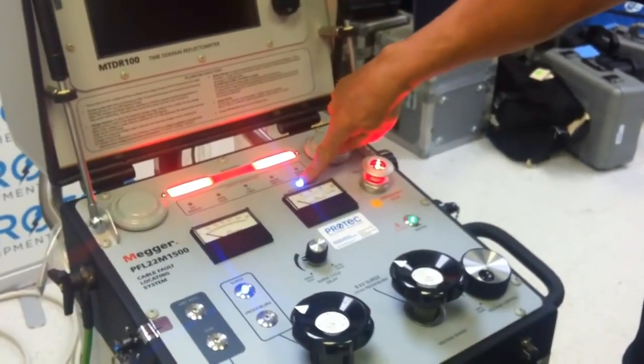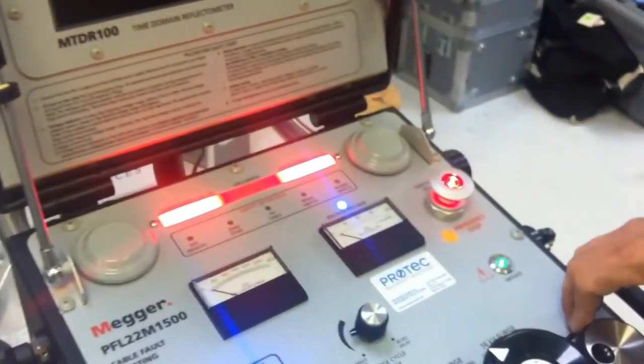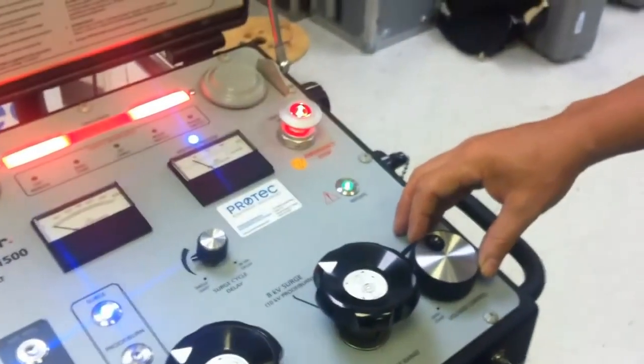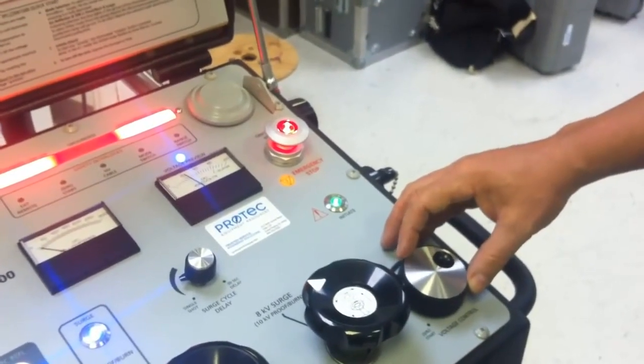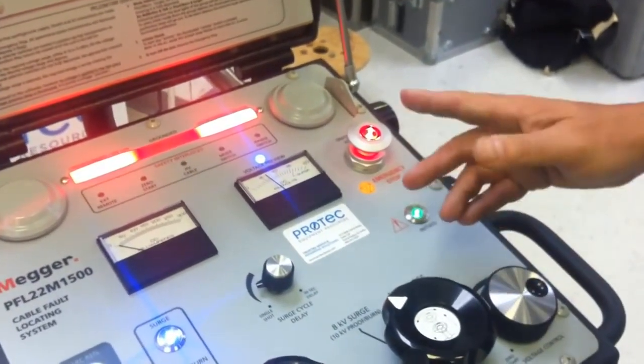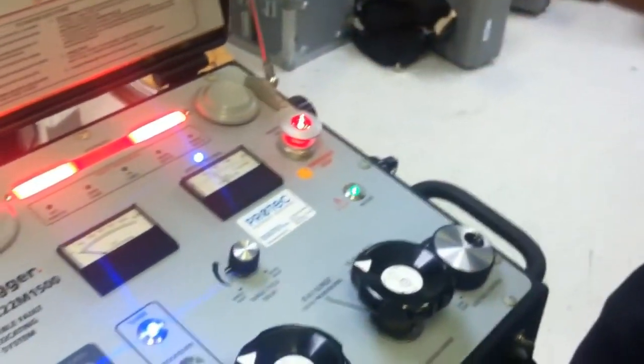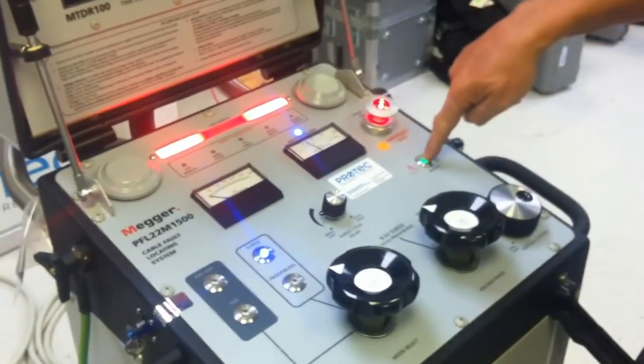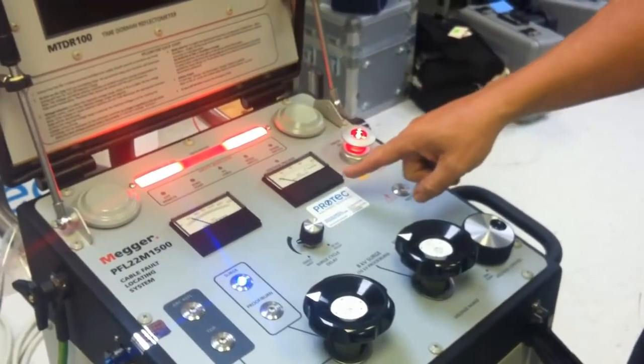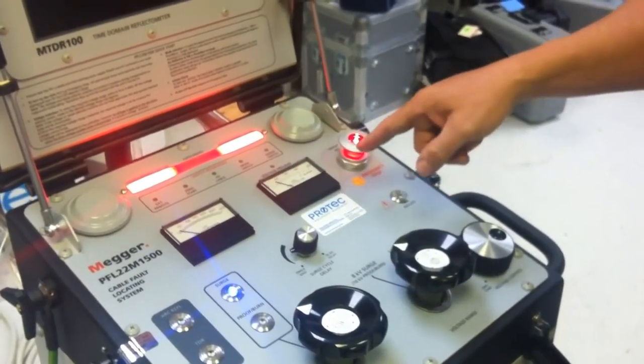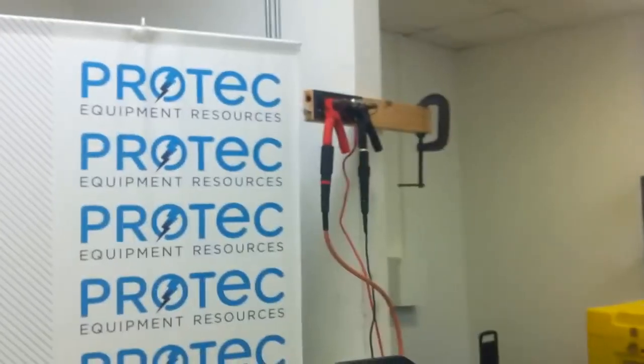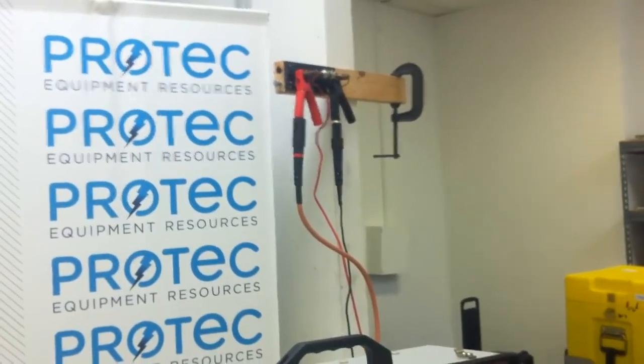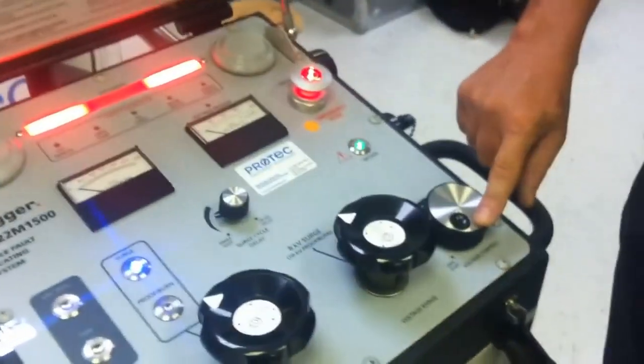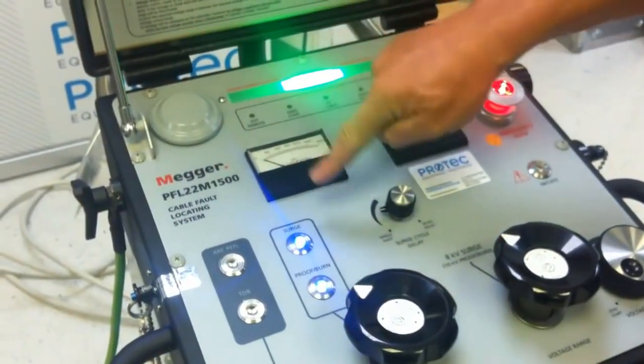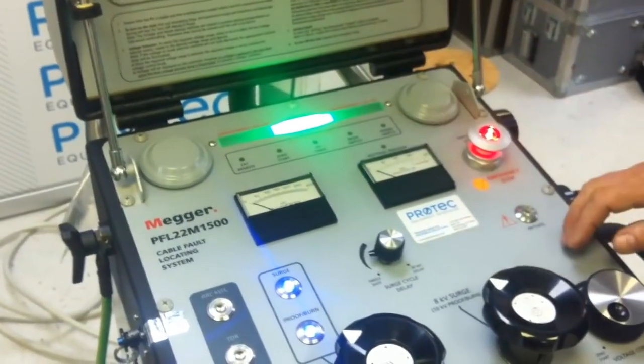Notice that the blue lamp tells me that I'm right now in a preview state. In a preview state, it allows me to go ahead and dial up to a level of voltage that I want to discharge at. I'm going to do it at approximately 6 kV. When I actually want to perform, I will then hit the initiate key. You'll now notice that the surge generator will charge itself to the preview value and will discharge at my spark gap. When I want to end the test, I'll bring it back to 0 and merely press my surge key one more time, and I'm back to a safe grounded state.